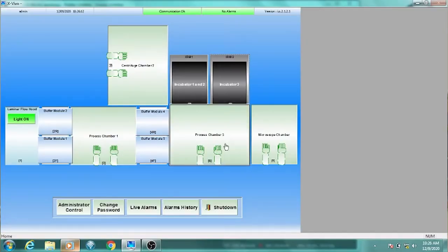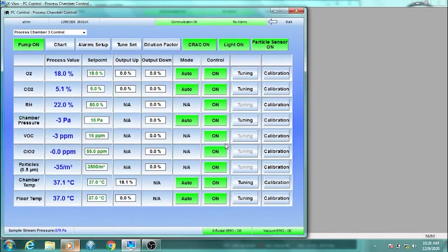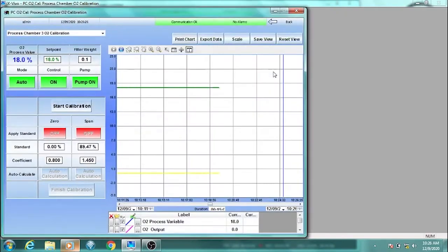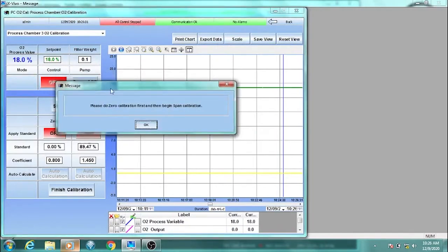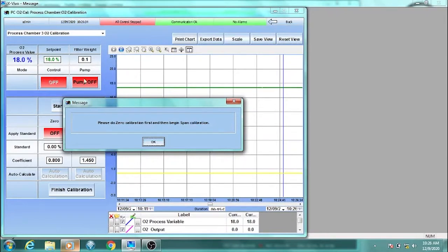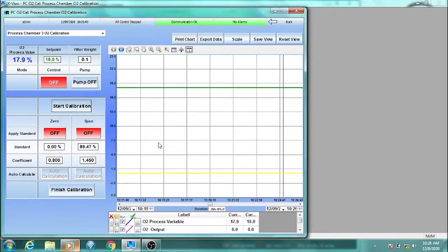Once you've logged into the software, go to the chamber you are checking the oxygen calibration in. Each module has their own sensors, and you will need to do a calibration check for them separately. Click the calibration button next to the oxygen sensor's reading. Click the Start Calibration button. The sample stream pump will automatically turn off. The software will notify you to do the zero calibration first, followed by span calibration.